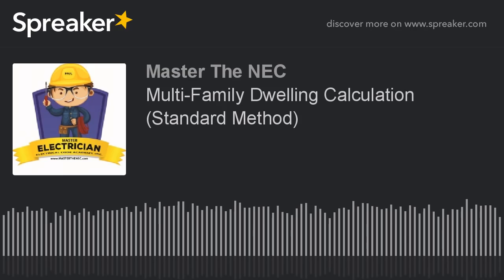Now it says here in table 220.42 that for dwelling units, I take that first 3,000 at 100%. So I take the 135,000 minus 3,000 times 100%, which is obviously 3,000. So that 3,000, I write that down. That is 100%. Now, when I took the 135,000 and subtracted that 3,000 at 100% from it, that left me with 132,000. Now, remember what it says here.